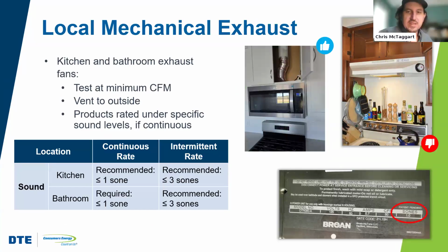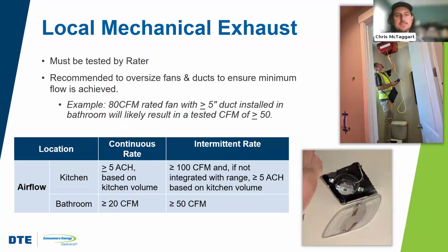Local mechanical exhaust is kind of the pair with whole house mechanical ventilation. So kitchens and bathrooms need to have specific air volume. Kitchens need to be ducted to outside. You can't just have a recirculating hood. That doesn't work. You have to actually send the air directly to outdoors. And depending on whether or not it's continuous or recommended, there is a sone requirement. These rates have to be tested. And these are unlike our whole house ventilation rates, which allow for a little bit of flexibility. These don't have quite as much flexibility.